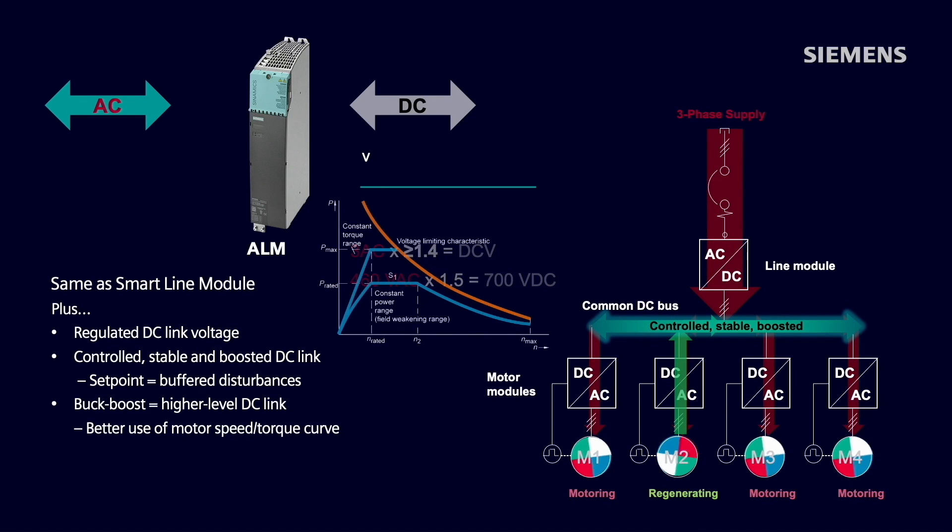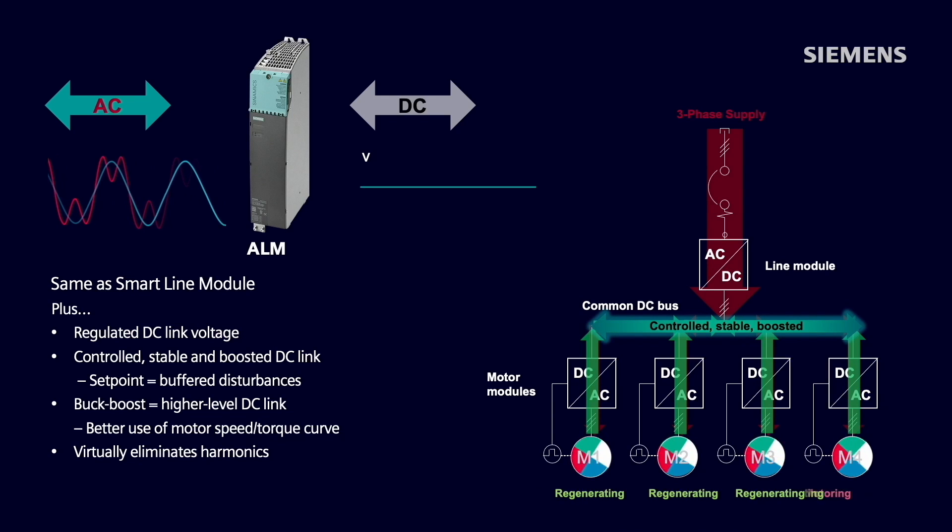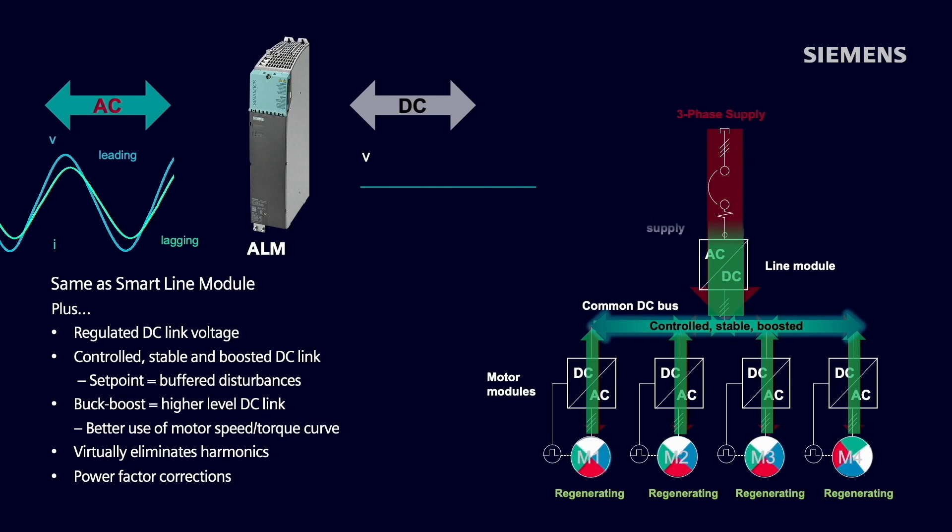Some additional advantages with the active line module include low line harmonics. The active interface module, which is used in combination with the ALM, provides line conditioning to virtually eliminate most harmonics. Additionally, this option allows us to do power factor correction. If we would like to have unity power factor from the drive system or a leading or lagging power factor, this can all be accomplished with the active line module. Having the capability to regulate the DC link with very little ripple on the DC link makes this the highest performance of the drive system selections.